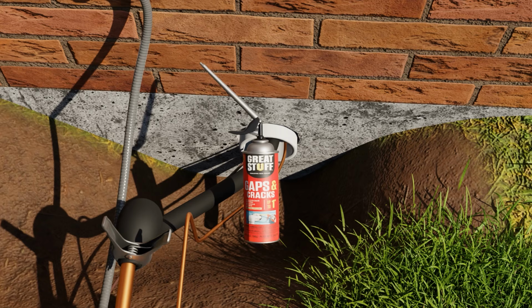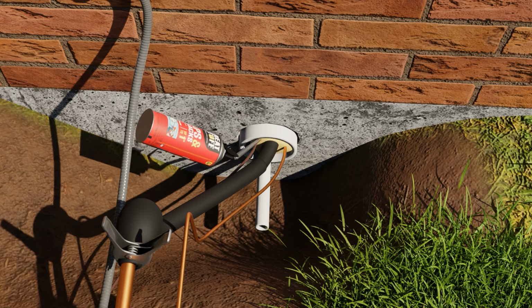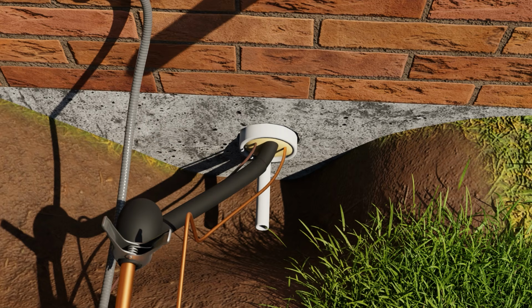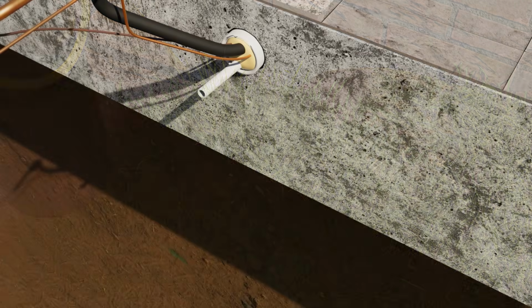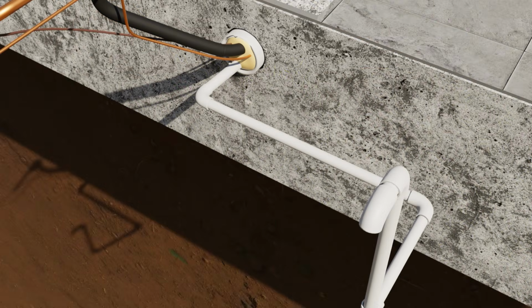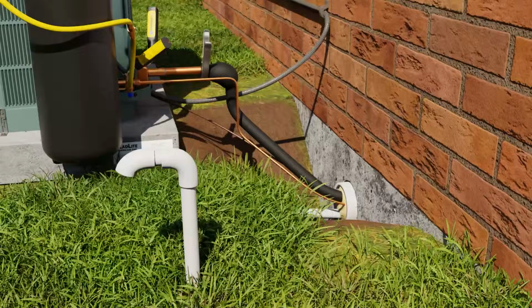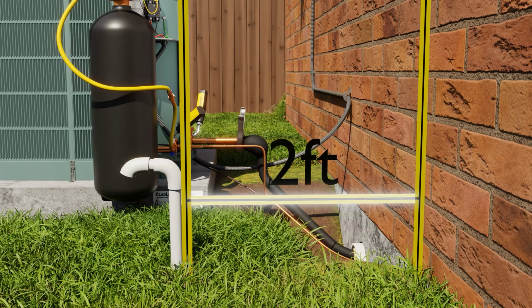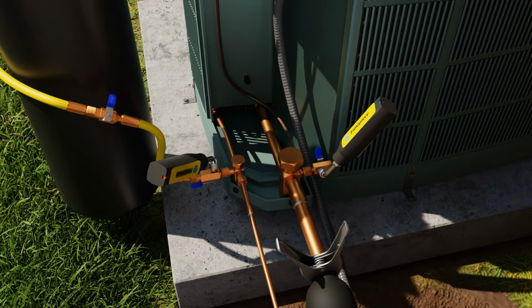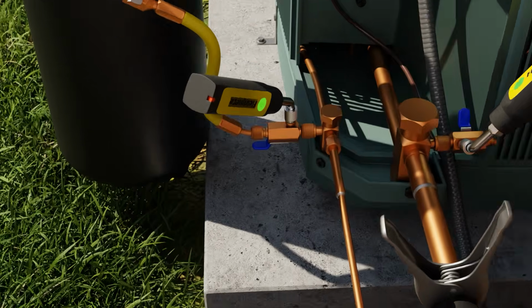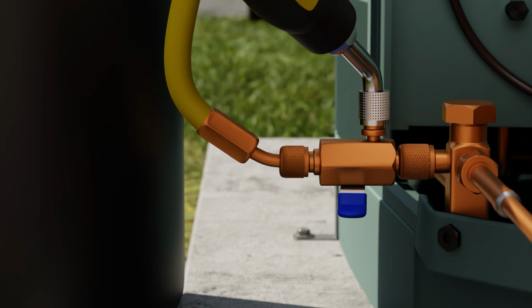In both cases, the sealing is really mostly for insects, just to make sure we're not going to get them into the space. It's not going to do a whole lot for water. When installing the drain in general, ensure that it's about 2 feet from the house if possible. You can bring it a little closer in some cases, but try to keep it away from the slab as much as you can. Once you've passed your pressure test, now you're okay to discharge your nitrogen and begin pulling your vacuum.